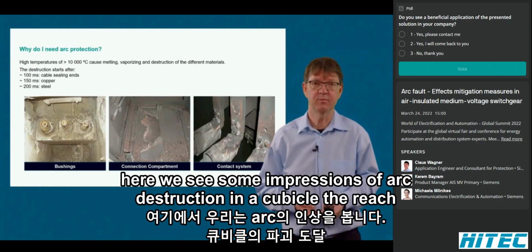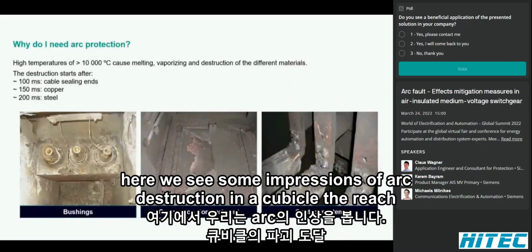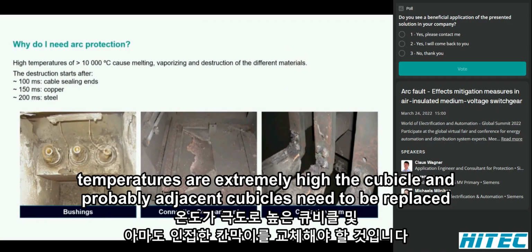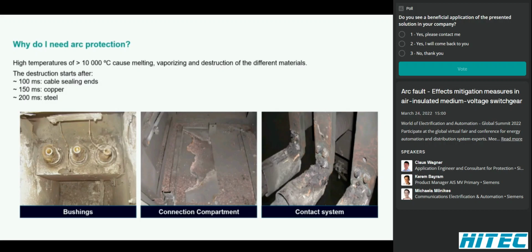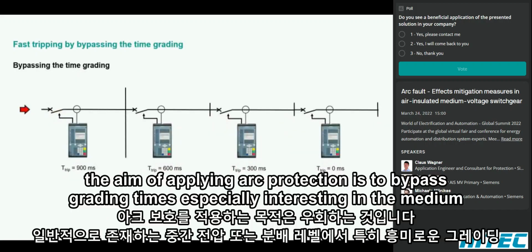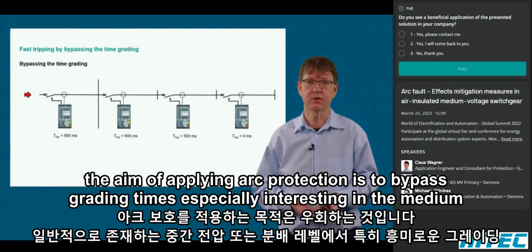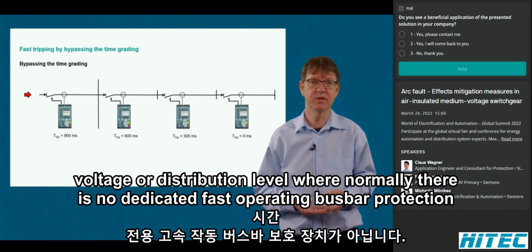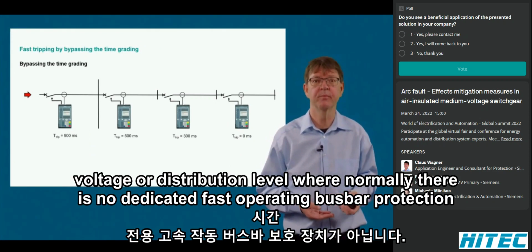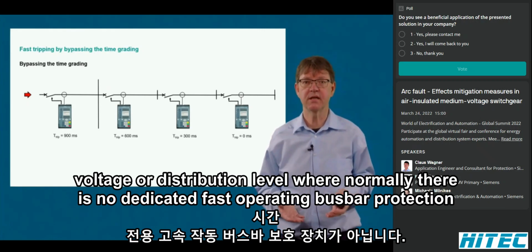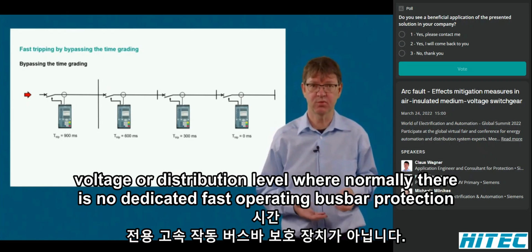Here we see some impressions of arc destruction in a cubicle. The reached temperatures are extremely high. The cubicle and probably adjacent cubicles need to be replaced. The aim of applying arc protection is to bypass grading times, especially interesting in the medium voltage or distribution level, where normally there is no dedicated fast operating busbar protection.